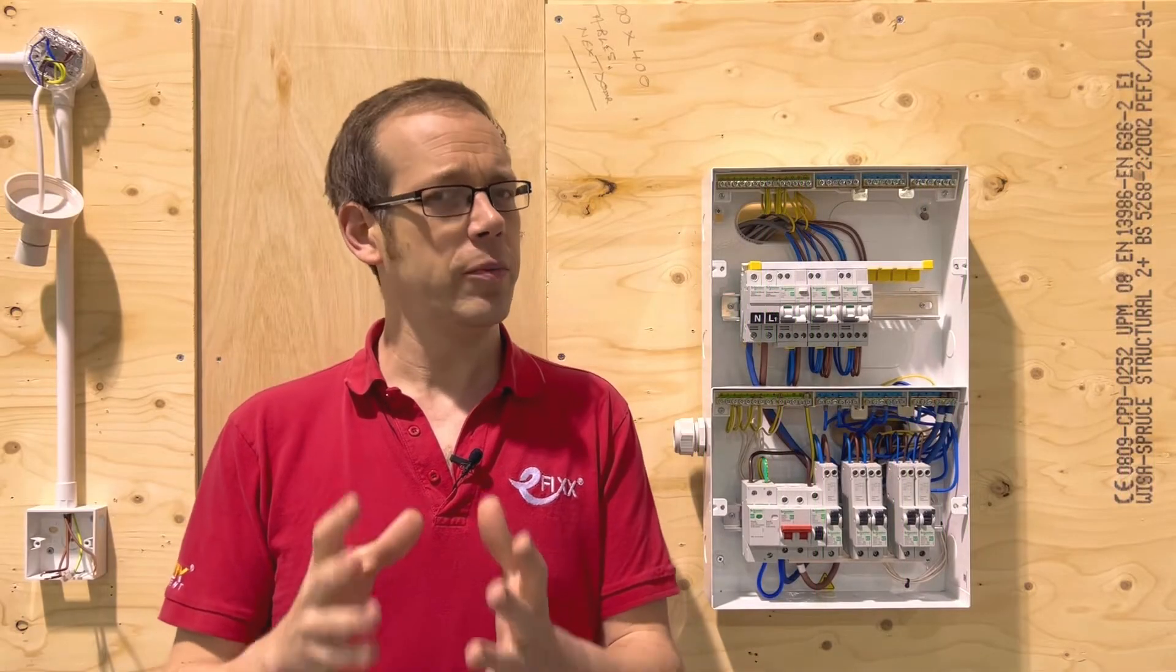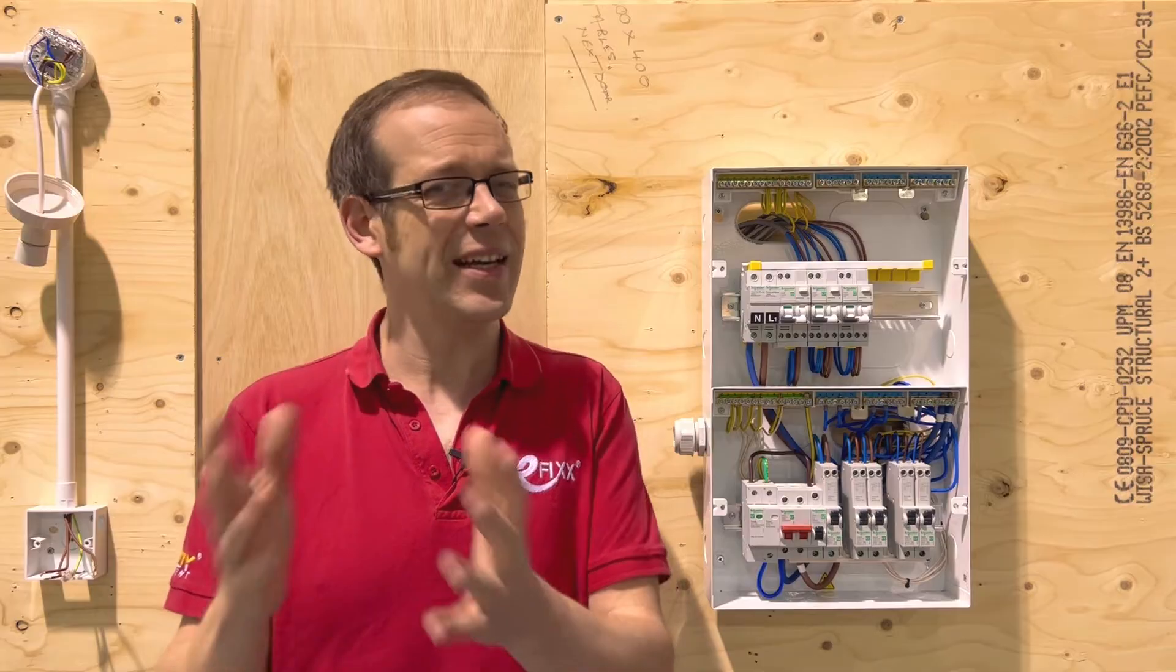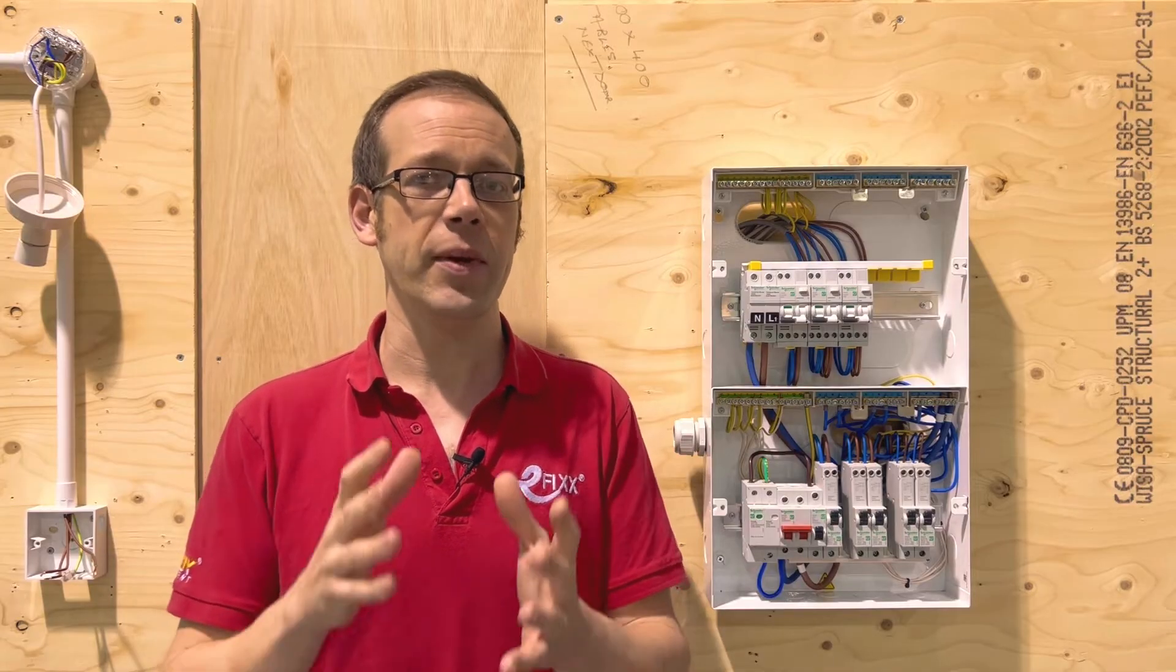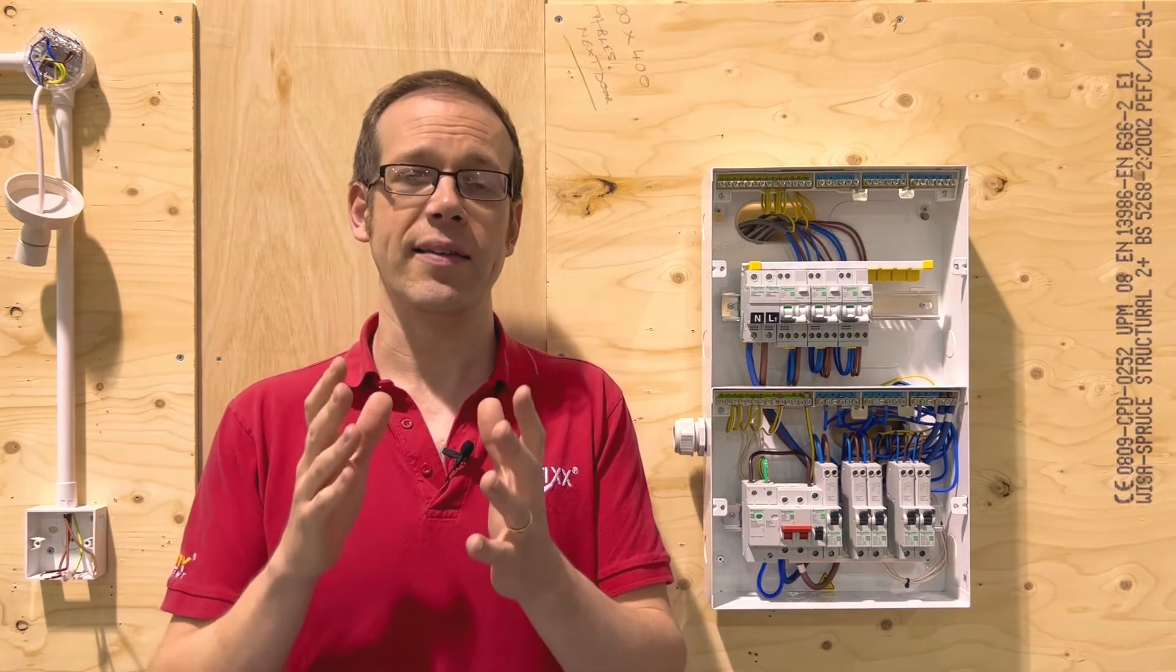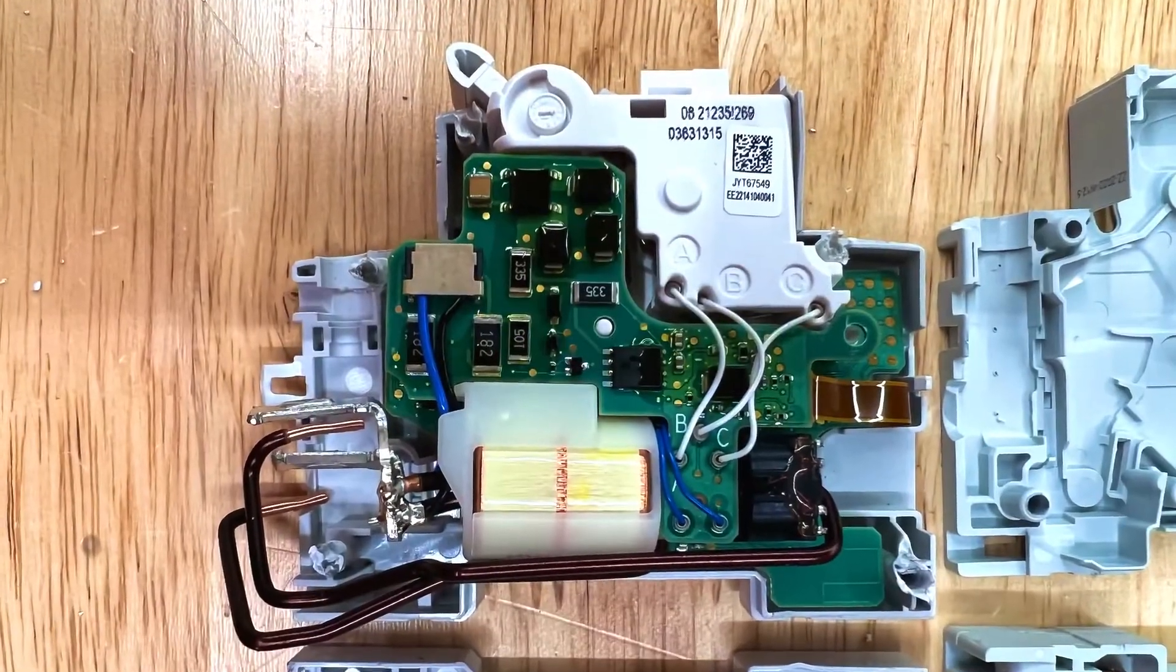Now while this messy waveform may look totally random it actually forms a fairly predictable shape like a signature in the flow of current that can be identified by software as the creation of an arc in a circuit and that really is the key to how an AFDD works.